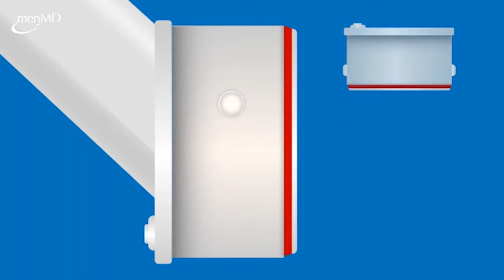The pump head has 2 small pegs on each side above the orange ring. These should be positioned into the 2 grooves on top of the penile tube. The 2 parts are then locked together with a twist, so that the 2 pegs slot down and locate at the lower end of the groove. If these two parts are locked together correctly, it will ensure the unit is sealed tight enough to create a vacuum inside the penile tube. To ensure a vacuum will be created, insert only your penis into the penile tube and apply slight pressure to the seal with the transfer sleeve against your body at the base of the penis.